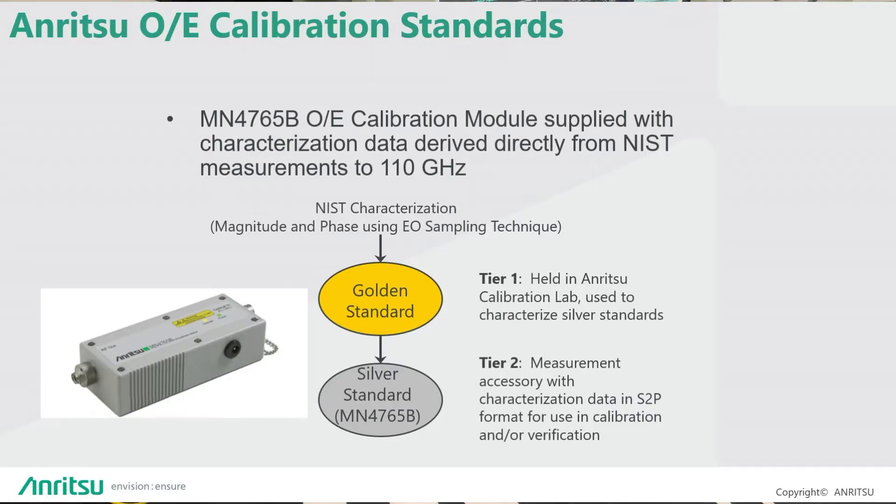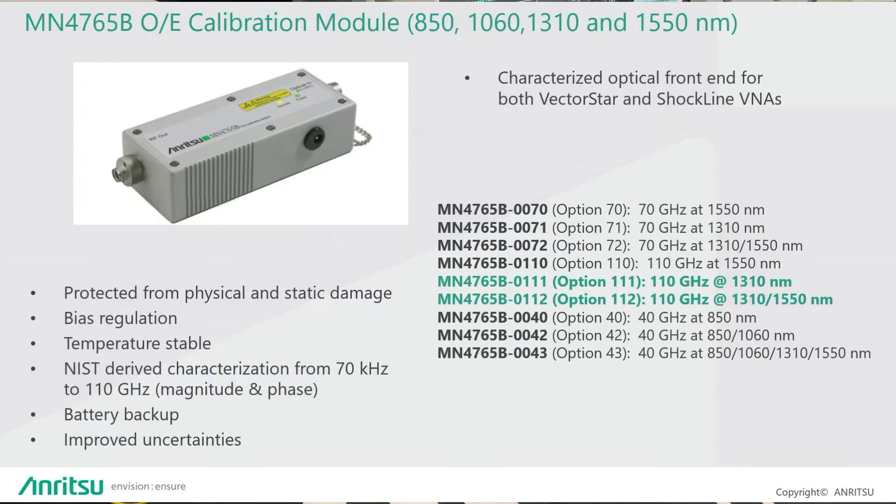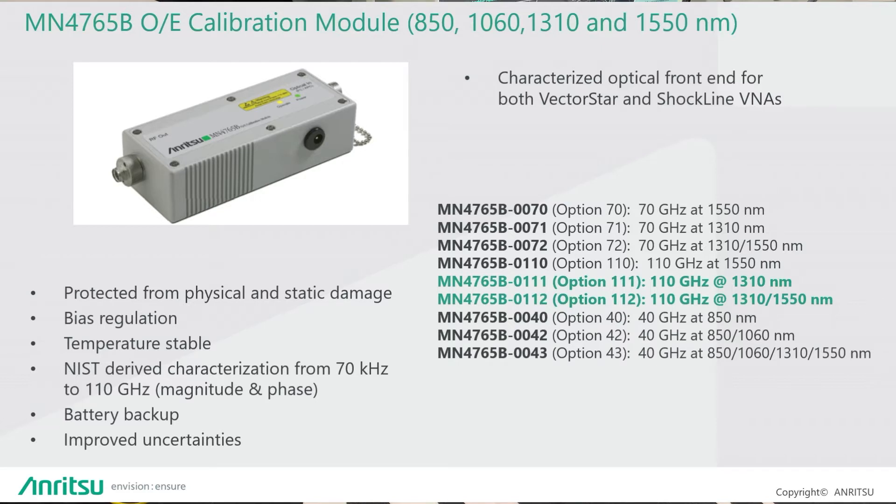How it works effectively is we have a characterized O2E module. This is traceable by NIST. It's held in our calibration standard lab and is our golden standard. And from this we derive S2P characterization files for all the O2E calibration modules. Various models are available, 40GHz, 70GHz, and 110GHz in various different wavelengths.